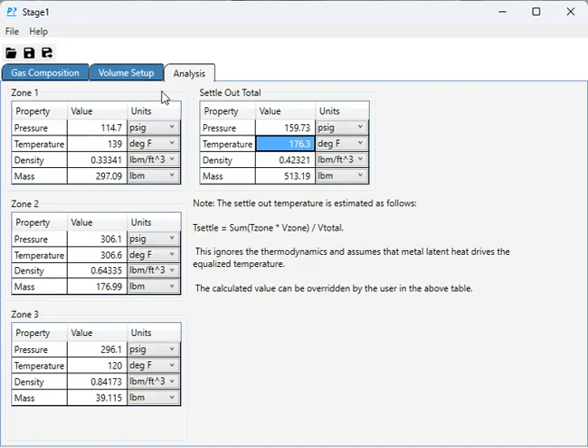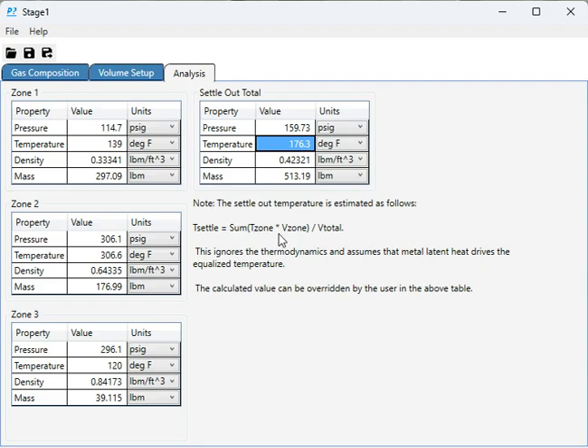Because I'm assuming the metal temperatures are driving the settle-out temperature, and the volume is representative of the mass of metal in each section. So simply the sum of the absolute temperatures times the volumes, divided by the total volume, and that's your settle-out temperature.